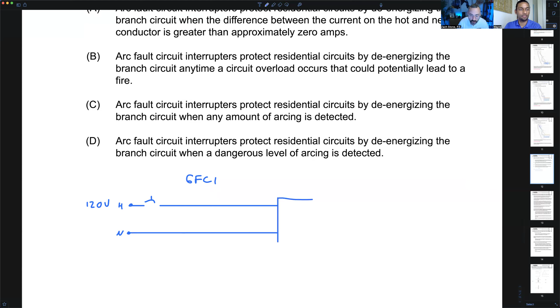So the way the GFCI works, whether it's built into the receptacle or built into the breaker, it's the same thing. It's essentially a special coil around both wires. Think of it as similar to a current transformer, where the wires go through it. Instead of one wire going through it, I've got two wires, my hot and my neutral.